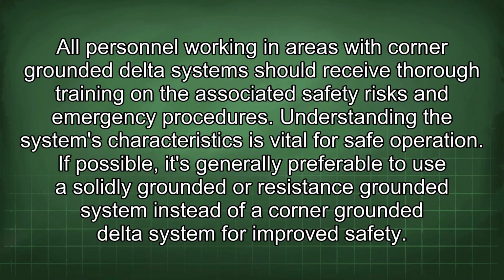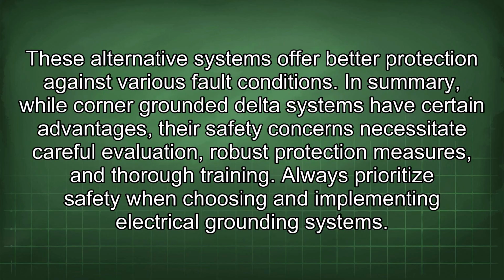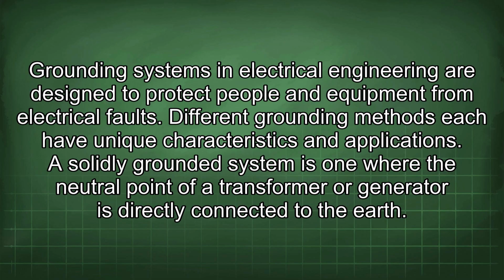If possible, it's generally preferable to use a solidly grounded or resistance-grounded system instead of a corner-grounded delta system for improved safety. These alternative systems offer better protection against various fault conditions. In summary, while corner-grounded delta systems have certain advantages, their safety concerns necessitate careful evaluation, robust protection measures, and thorough training. Always prioritize safety when choosing and implementing electrical grounding systems. Grounding systems in electrical engineering are designed to protect people and equipment from electrical faults. Different grounding methods each have unique characteristics and applications.